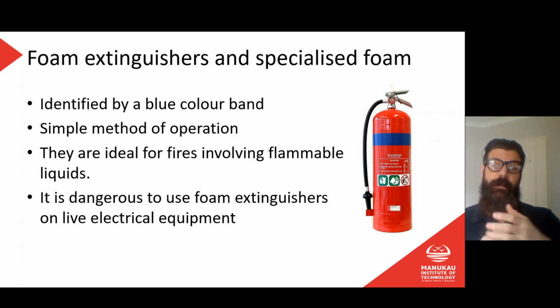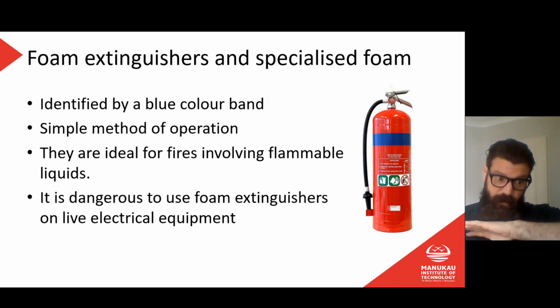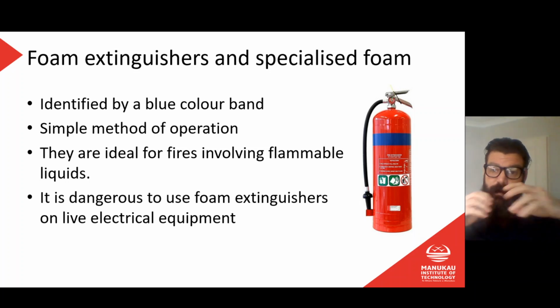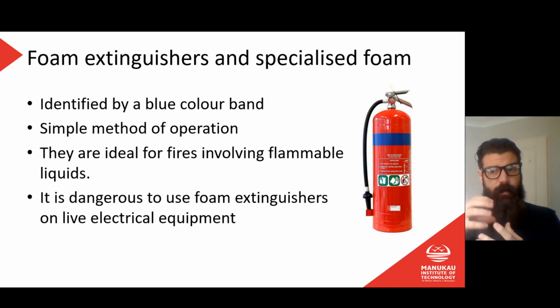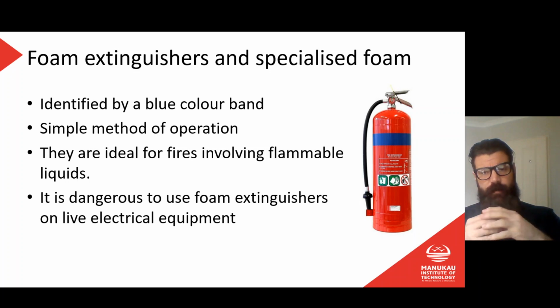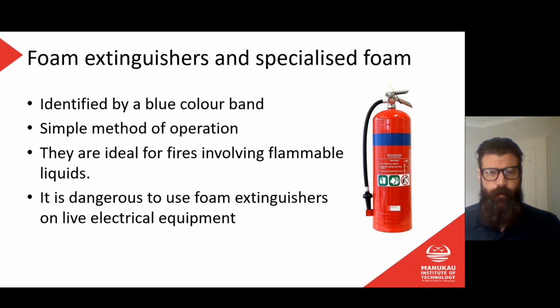They have the advantage of the dry powder in that they're smothering the fire. What we've got in there is no actual foam. The foam is created as a reaction between two compounds, which are released when you open that valve, and then it expands very rapidly into a very light foam which will sit on top of the fire and smother it from oxygen like the dry powder.